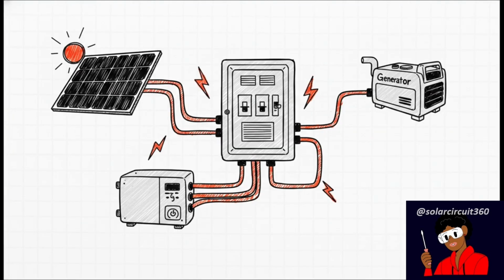Now you might be thinking, well, the utility grid rarely changes its phase rotation, so why is this such a common issue today? Good question. The answer really lies in the sheer complexity of modern power systems. A technician might unwittingly introduce a reversed phase sequence in a bunch of different ways. Say you're upgrading or replacing a massive three-phase hybrid inverter. The new inverter's internal terminal sequence might actually differ from the old one.